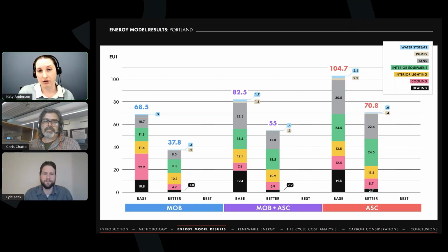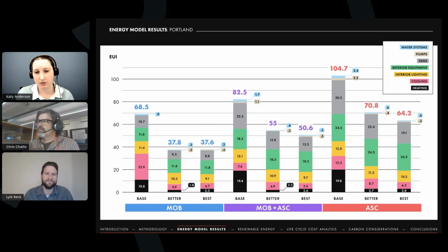We do setbacks overnight in the surgery center, and we can reduce the hours of airflow delivery in the blue due to segregating more of the air handlers, so we can have better controllability of when things are on and off, as well as on the plant side with those heat recovery chillers. All of those things are contributing to a big improvement in the amount of plant energy used, the pink and the black.